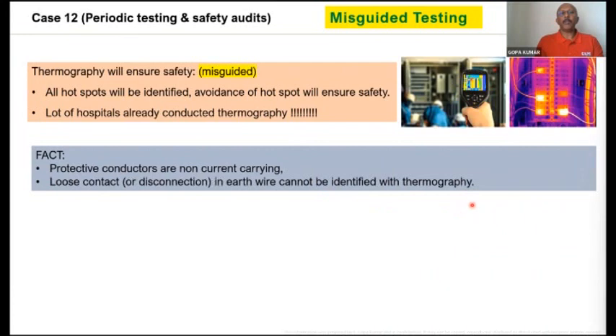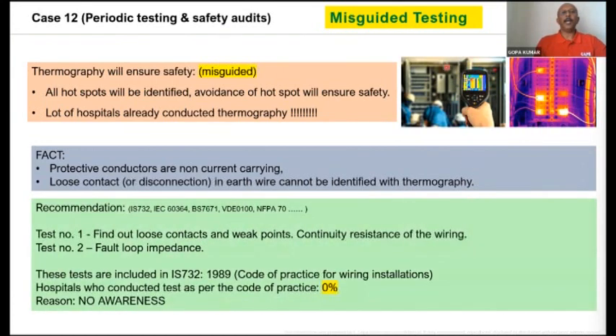Why I am showing this picture again is that some of the builders, some of the high-rise buildings in Bombay, started doing thermography because they think that by doing thermography, everything becomes normal, or you can find out the loose contacts. This is what they think. Absolutely no. Most of the time, when the fault is happening, the current is flowing through the earth wire, which is normally a dead wire. With thermography, you cannot find out the heat produced in a dead wire because it's dead. So this will actually misguide you. Please don't do it. Before that, you do all the 10 tests as per the IS 732, and probably after that, you do it as an additional safety thing.